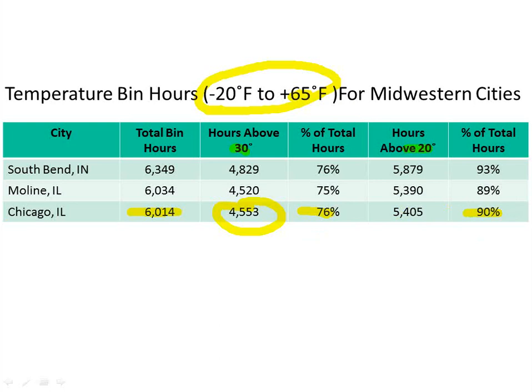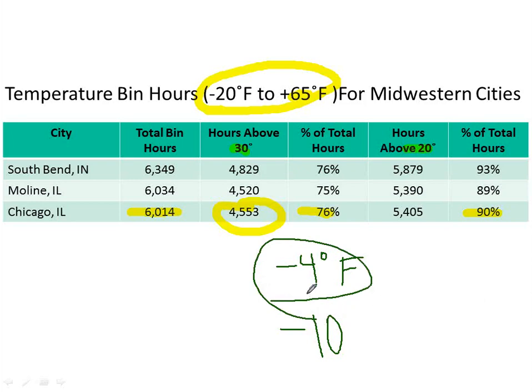Well, unfortunately, we can't size your furnace for 20 degrees outside. Because at 20 degrees outside, I'm never going to heat you on the coldest day of the year. If you look at the ASHRAE handbook, depending on which city you're in, you're probably going to see -3, -4, -5 degrees as our design temp. So that's what we need to be designing for. I know some of you old school guys are still using -10. That is not correct, nor is it generally permitted by the new energy code. You need to use the current city data for the 99% value.